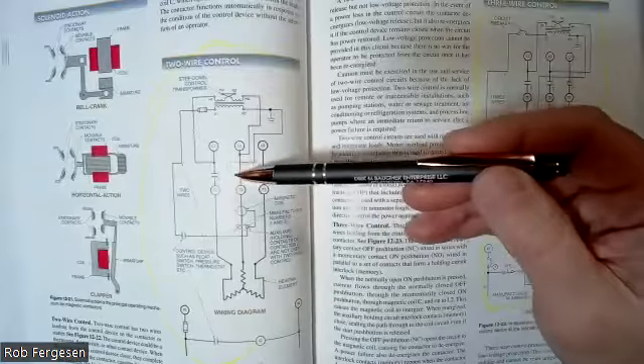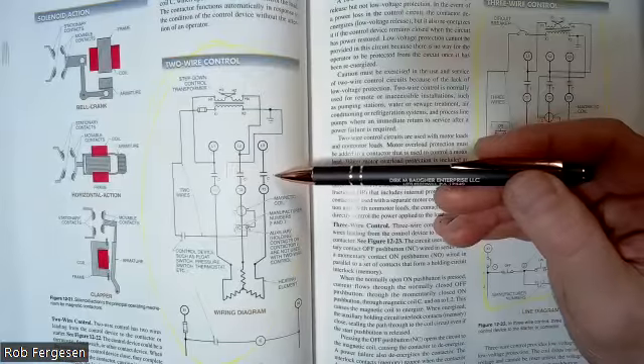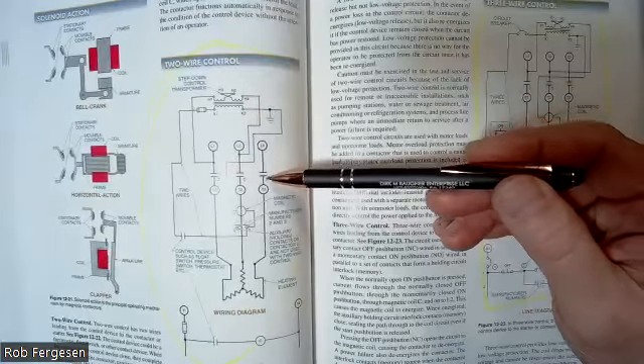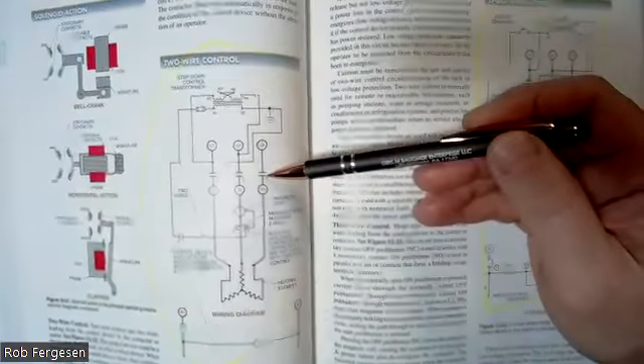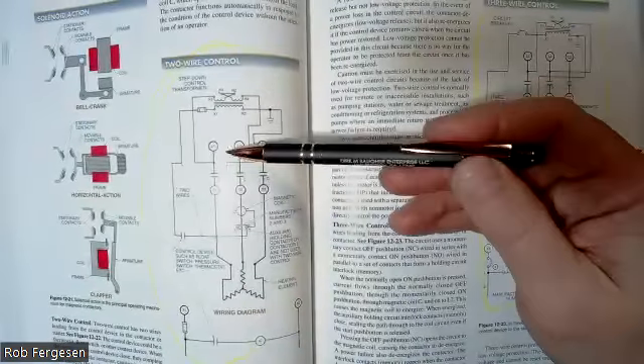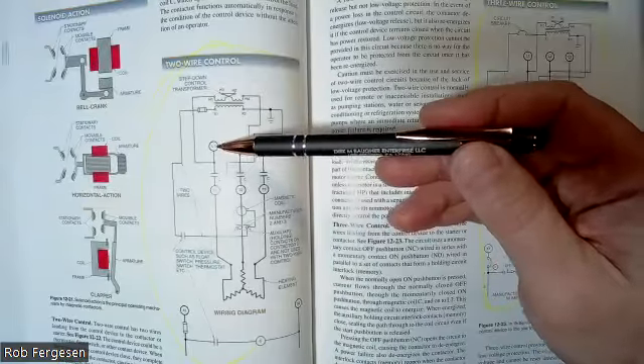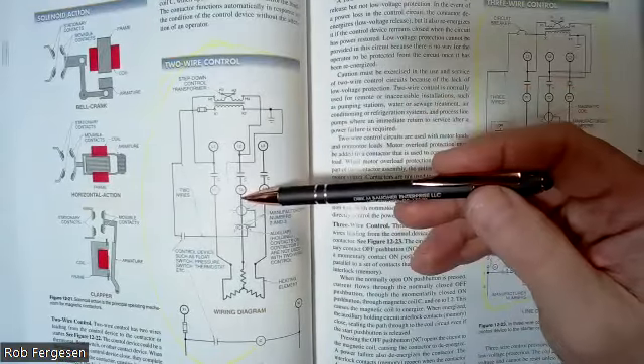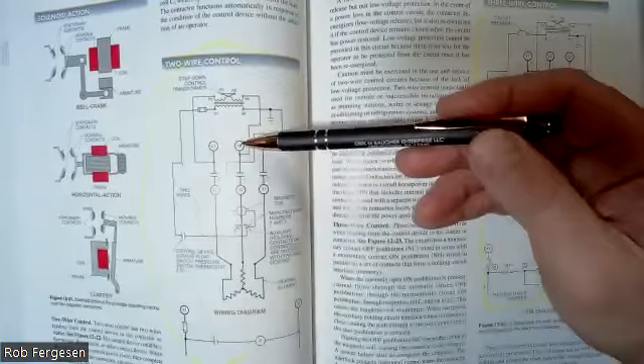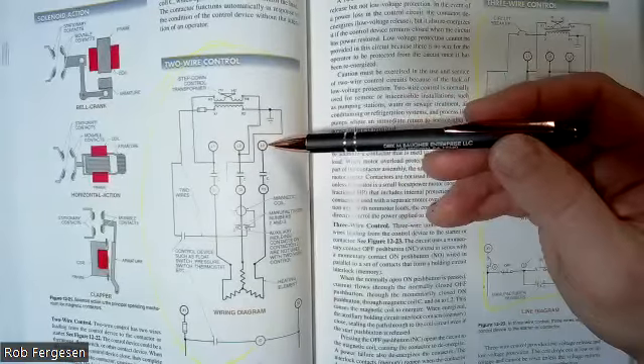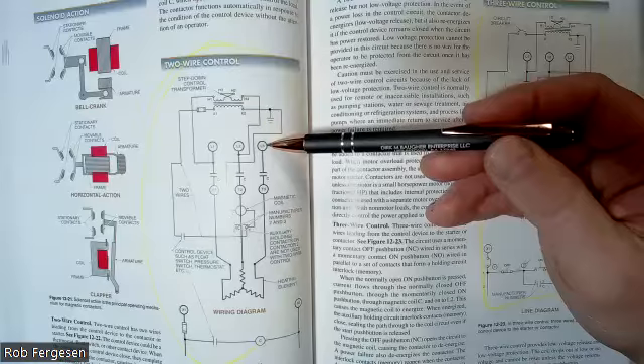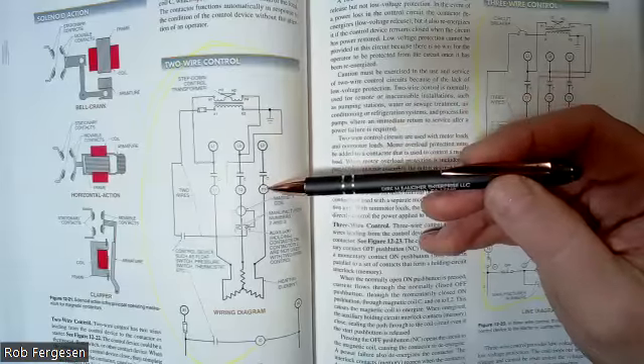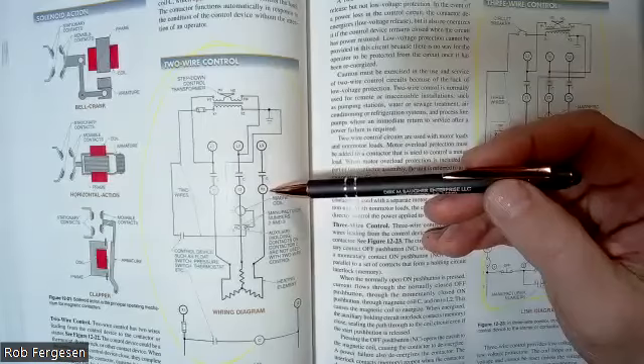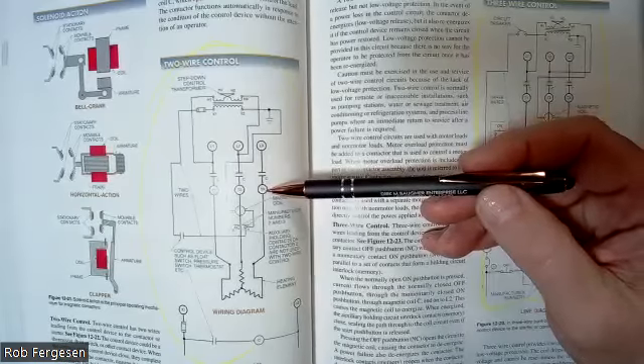You can see these 3 contact points in the diagram. They put a little C next to it, but you don't always see a little C. In fact, the little C is rather uncommon. They give you the labeling of the input and output of the contactor. L1, L2, L3 are pretty typical inputs. Those are hooked to your legs. T1, T2, and T3 are pretty typical labeling for outputs. They go to your motor or whatever your load is.